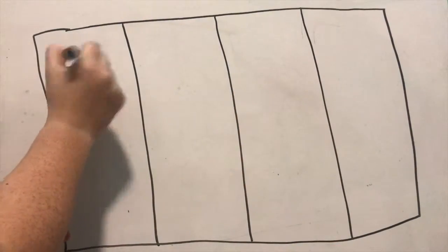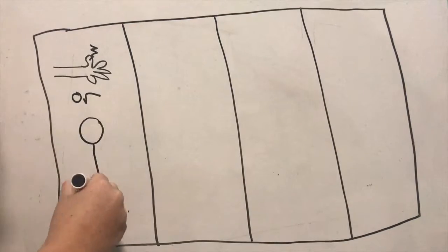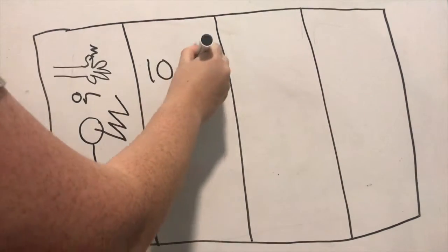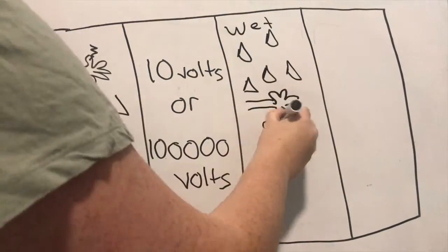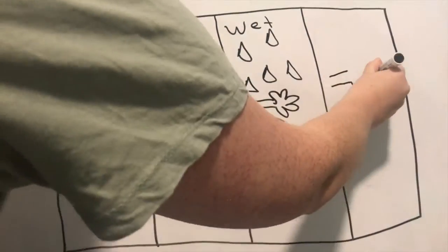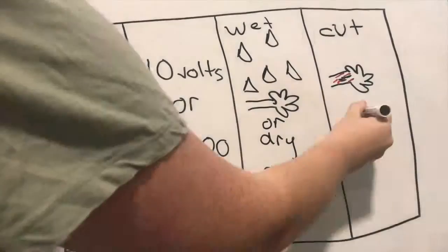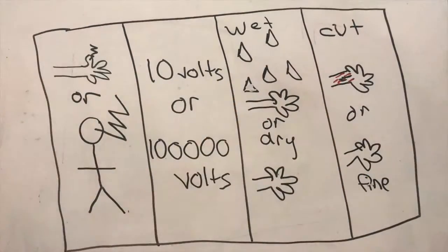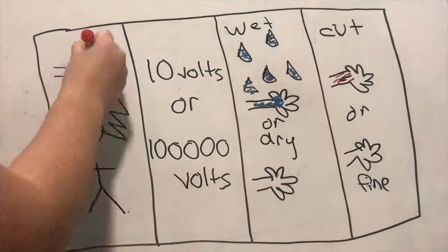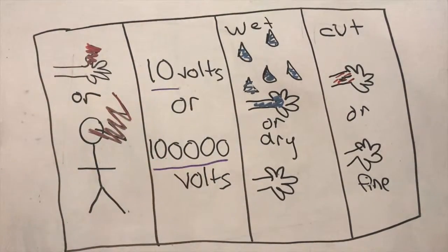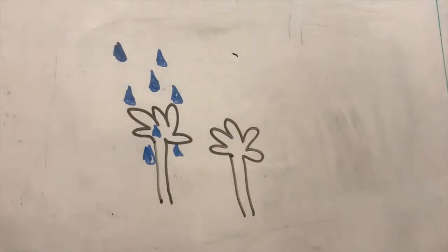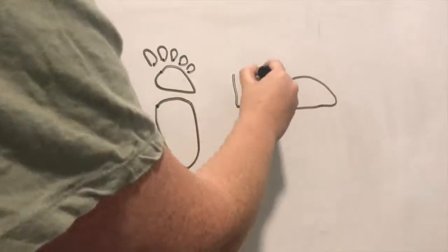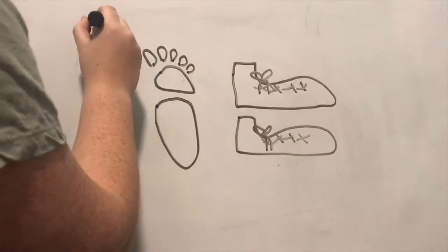The resistance of the human body is determined by the surface area of contact, voltage applied, and whether the skin is wet or dry. Lower voltages are safer in maximizing the resistance of the skin. The voltage dependence of skin resistance is due to electroporation, where pores in the skin cell membranes open due to the applied voltage and increase in diameter as the applied voltage increases. Wet skin has a much lower resistance than dry skin. Wearing insulating shoes also increases the total resistance of the body. For example, rubber shoes have a much higher resistance than leather shoes.